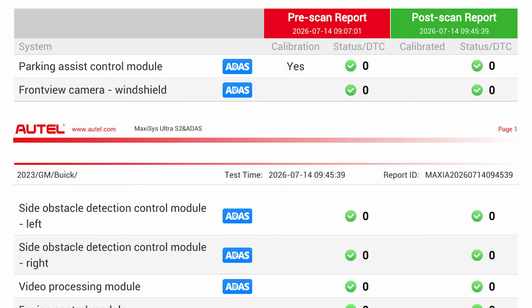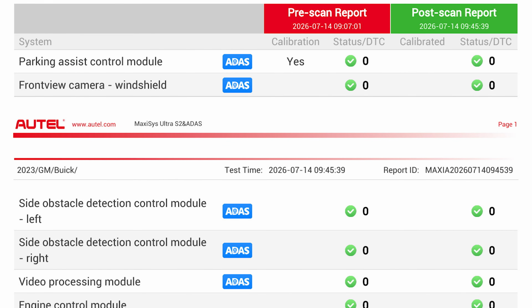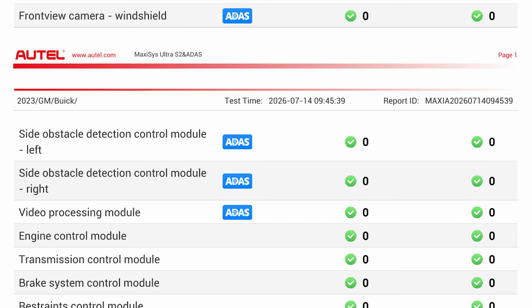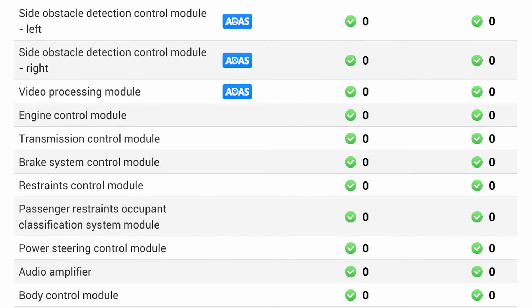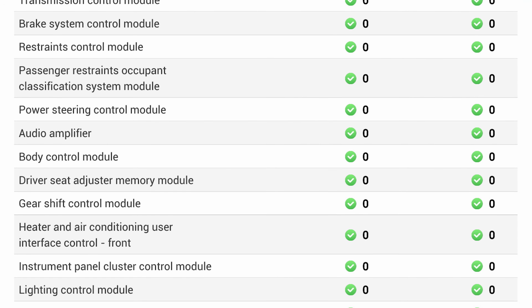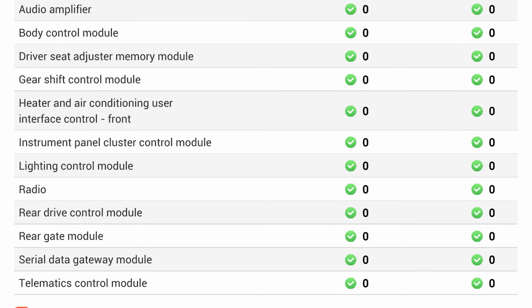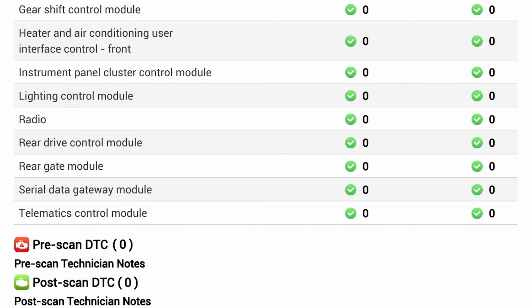Now, of course, with any calibration that you do, you want to make sure you test drive it, make sure the system is operating as designed before you return it to the customer, and of course, do that post-scan so that you can give your customer a copy of the report that shows pre-scan, post-scan, and of course, the calibration was completed successfully.